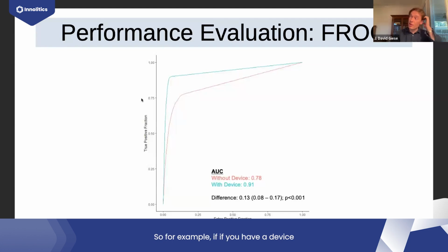So for example, if you have a device whose functionality might depend on body mass, then you'll definitely need to make sure you have enough samples of different types of body mass. Or if there's different types of lesions, like different disease states, you might need to cover that. Or ethnicity is another one. So that's really common. In imaging studies, different MRI scanner manufacturers is another. And so there can be a long list of sources of variability. And I would say in a lot of cases, it seems like 150 to 250 is a pretty common number of cases you need, but it really can vary a lot.